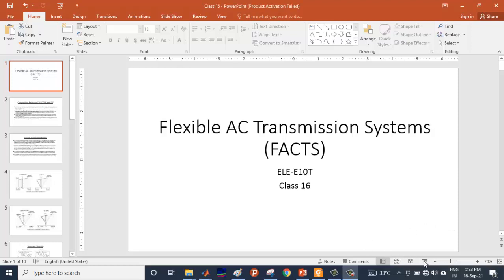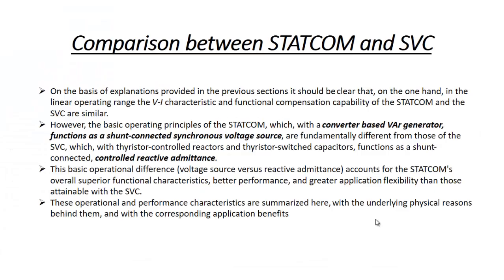Welcome to the new lecture. In this lecture we will be discussing about the comparison of the two shunt compensators, that is the STATCOM and the SVC. As we have discussed earlier, in the linear operating range of the VI characteristics, the functional compensation capability provided by STATCOM and SVC are typically similar. Both of them are trying to maintain the voltage at the reference value. In the VI characteristics of both compensators, we have a horizontal line which is parallel to the current axis.